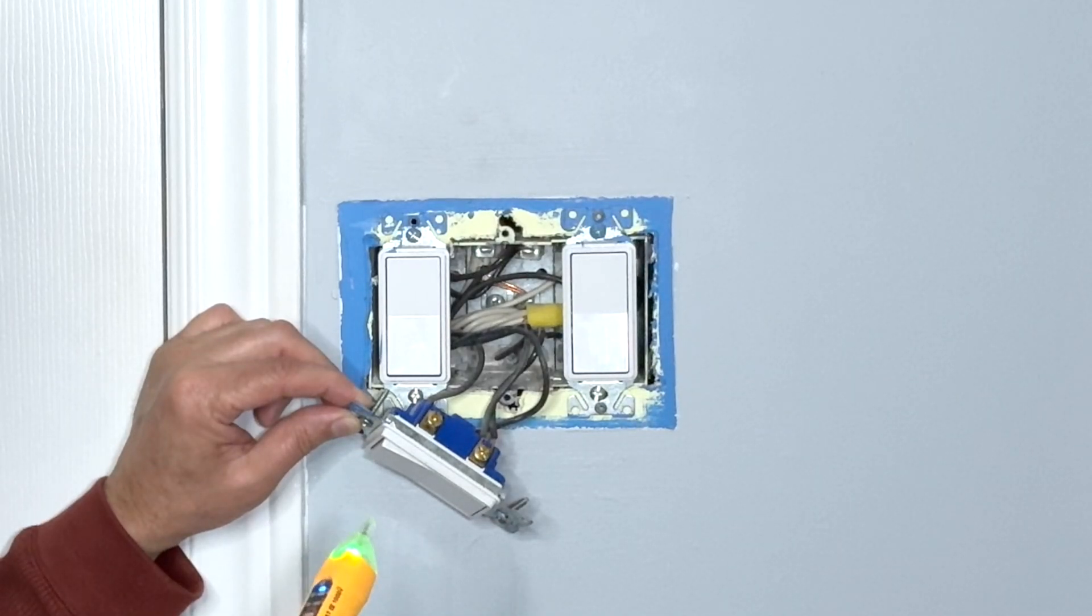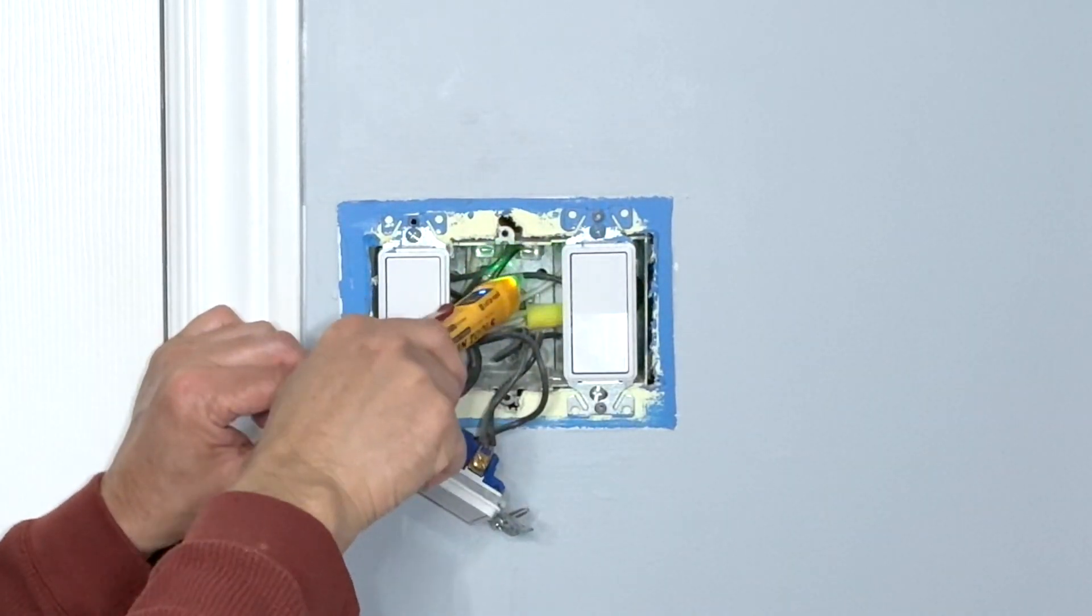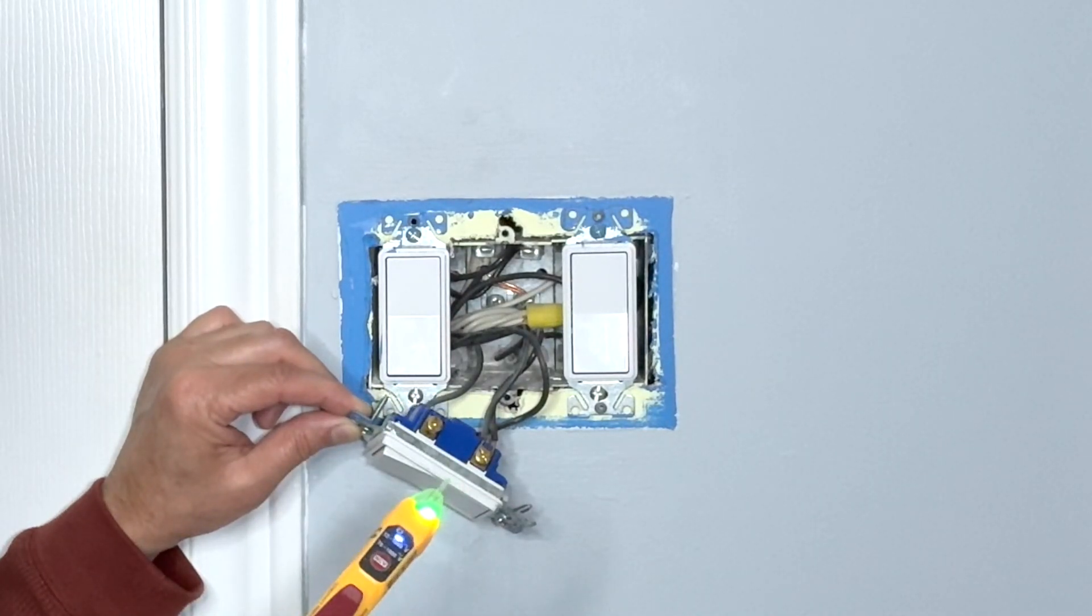Check one more time on the switch terminals as well as inside the box to make sure that there is really no power. It did not beep. The LED light did not turn red. That means there's no power and it is safe to proceed.